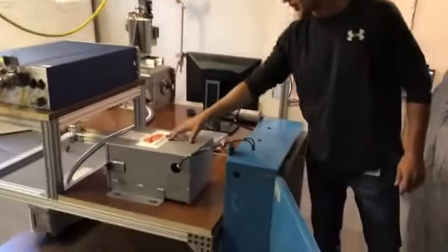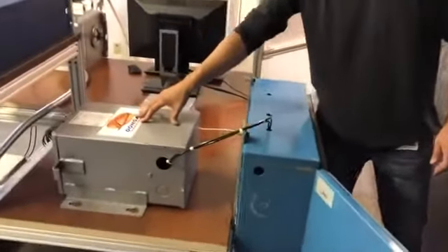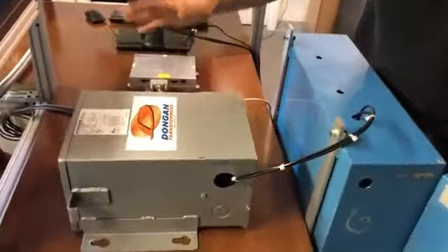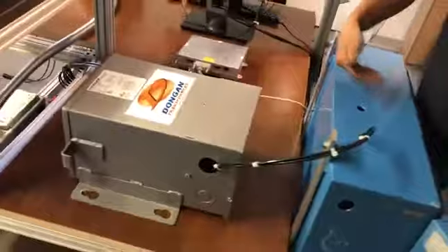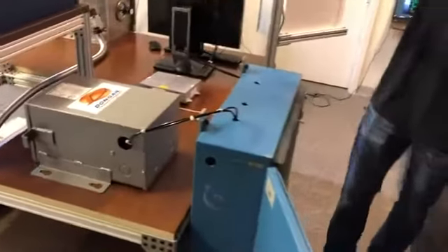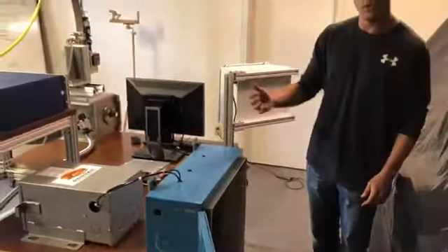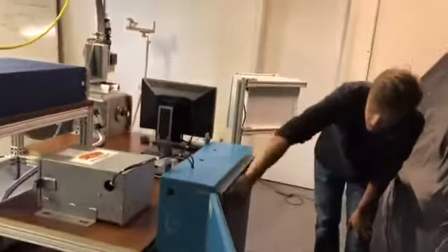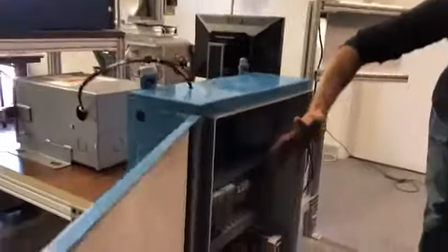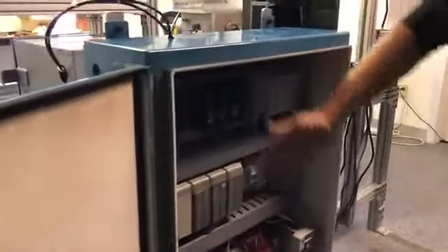Right here is a single phase 10 kilowatt transformer. Like I said, we're going to have our 240 coming into it, and the secondary output is going to be 120. That is then going to come through our second distribution block. From there, once we have our 120, we can power our 24 volt power supply and pretty much power any component in our system.